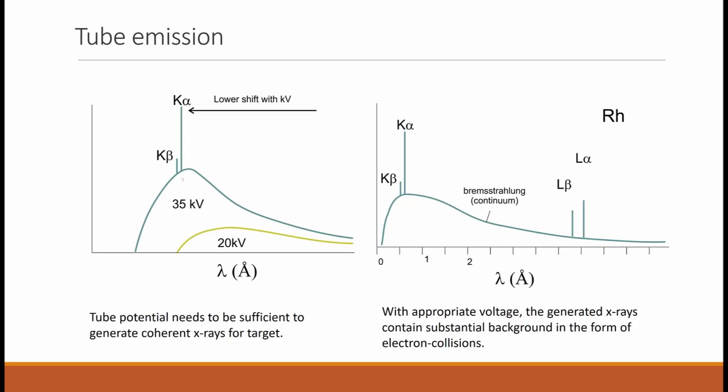We're after this peak right here, known as K alpha. There will also be a corresponding K beta peak very close to that, and we can't really stop that, except we can fish it out of the signal. And we will do so in our instrument with a quartz crystal that does a little diffracting on its own in the way of detecting.